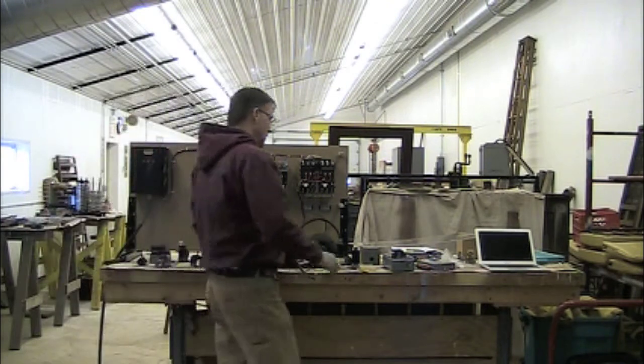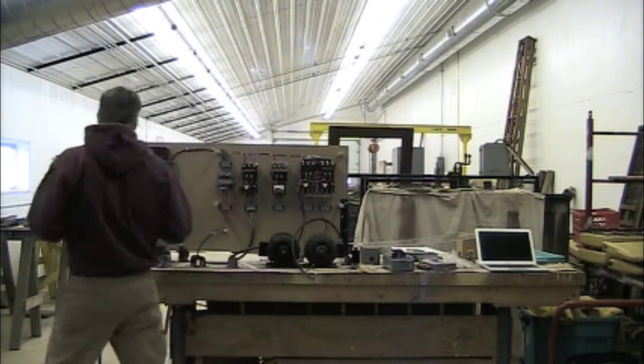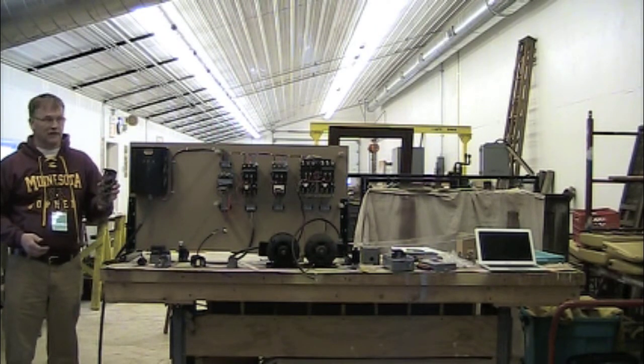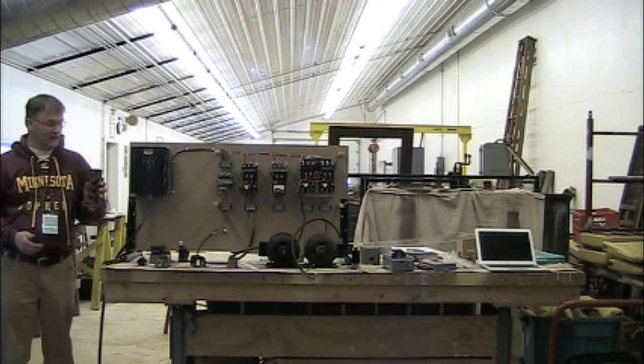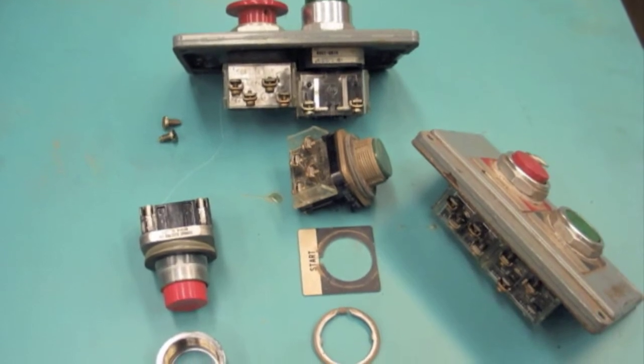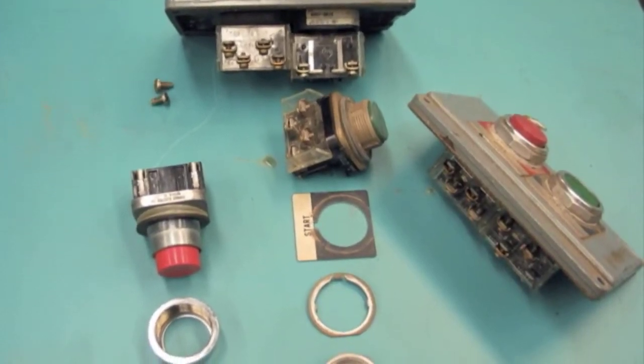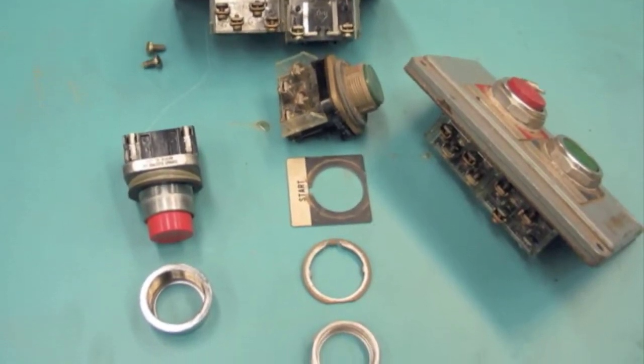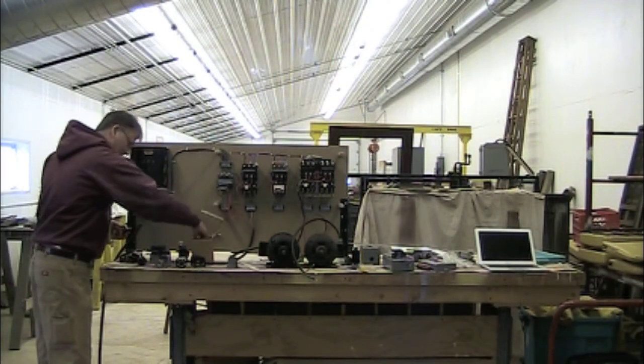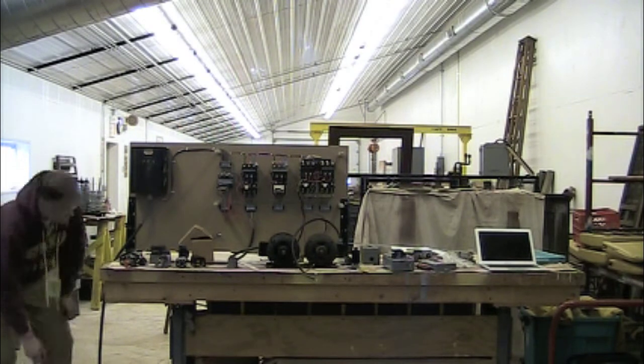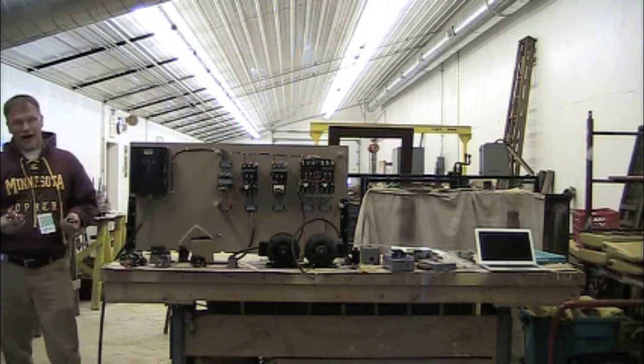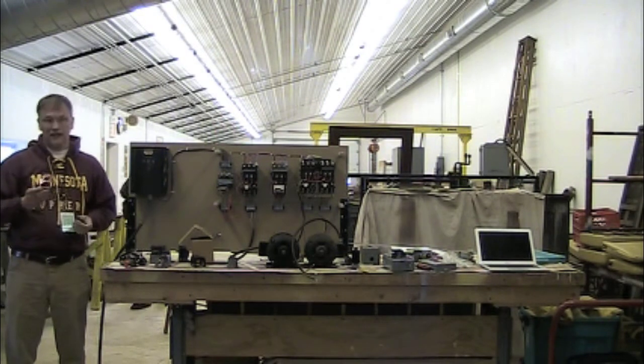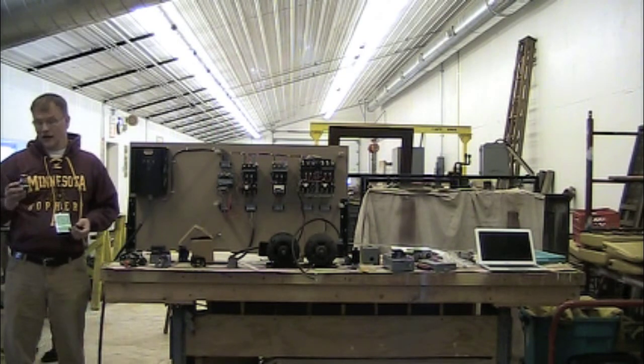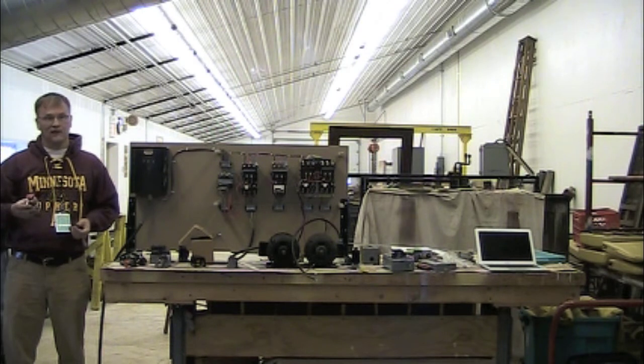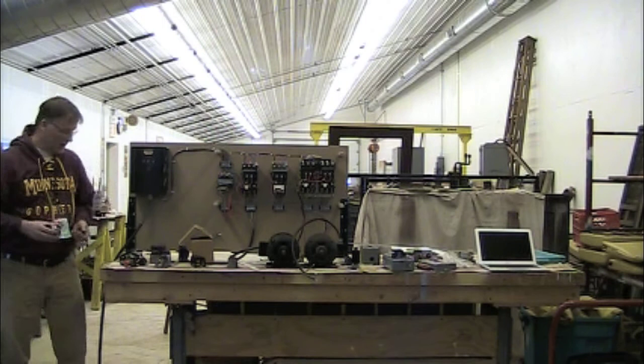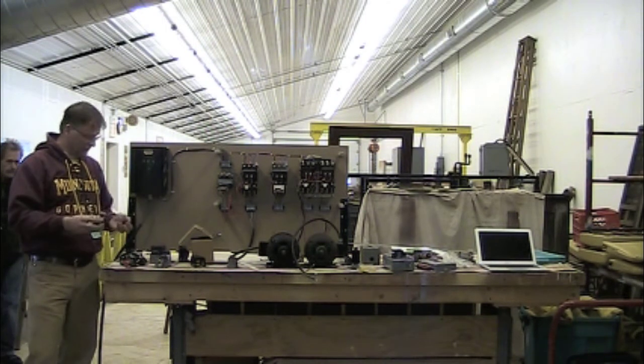But a lot of things that you'll find are made up of a bunch of different operator buttons that can be set up for different functions, and so you can change out the different buttons and what you're looking to do with it. So I'll show a few of them. So in all the different manufacturers, this stuff is all Allen Bradley stuff. Like I said, these are all 30 millimeter operators. There's 30 millimeter, 22, and there's little 16s. These are all the standard NEMA size, or the 30 millimeter. The 22s are used for a lot of NEMA stuff, but those are actually from the IEC standard, so that's a European standard. But within the 30 millimeter stuff, it's all fairly similar between the manufacturers.